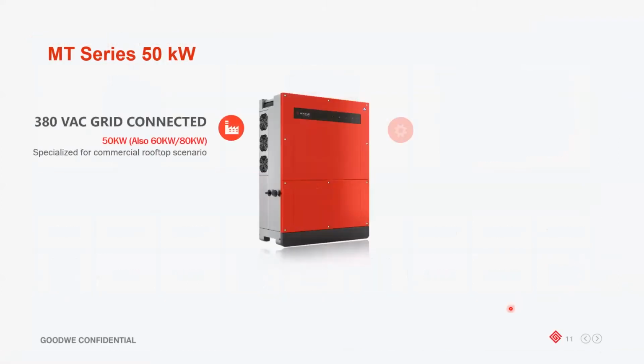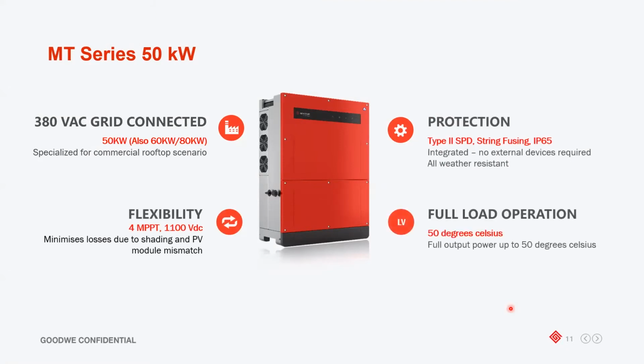So the MT series inverter, which I mentioned is available in 50, 60, and 80 kilowatts, has been to date our most popular inverter for commercial PV plants and industrial and large scale PV farms, for anywhere from 50 kilowatts to 20 megawatts. So its low voltage output is specifically designed for commercial and industrial applications. That means no external step-up transformer is required. It comes with 4 MPPTs, with type 2 surge protection, and string fusing is also equipped as a standard for Europe. By virtue of the fans that we use on the side, the inverter has a full load operation of up to 50 degrees, which is significantly higher than inverters that are designed with no active cooling.